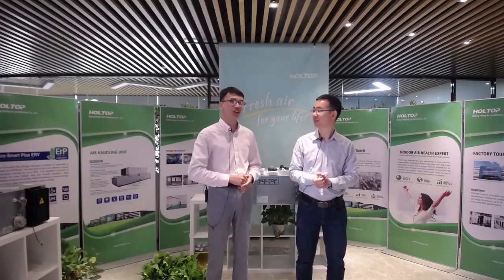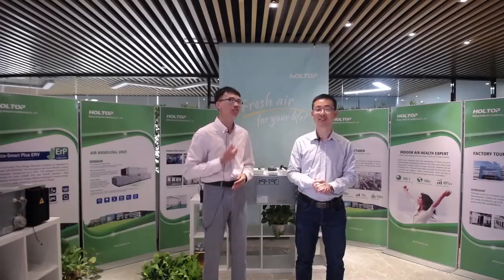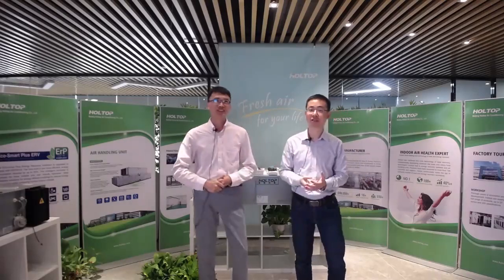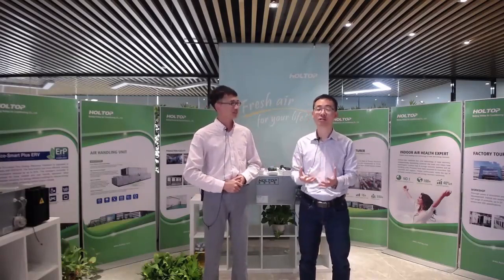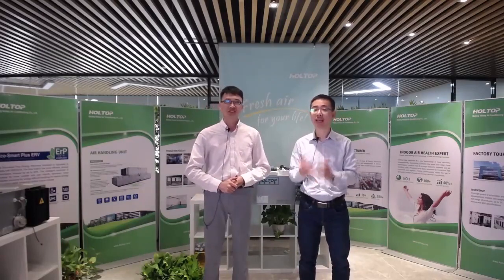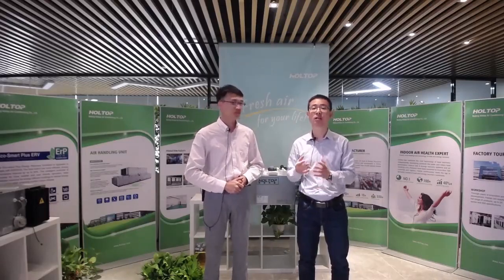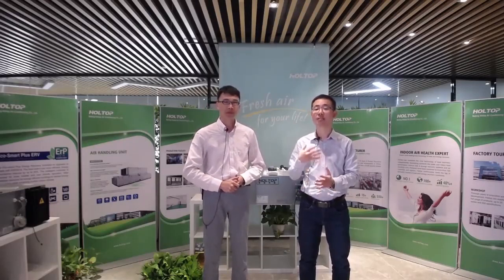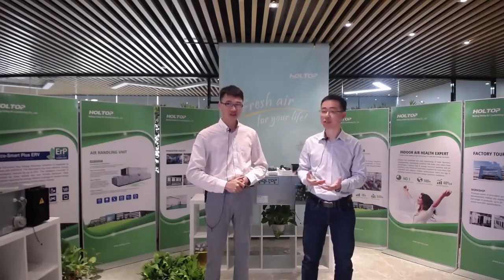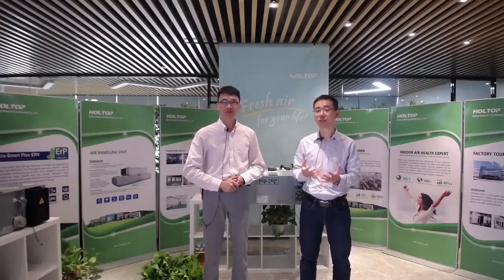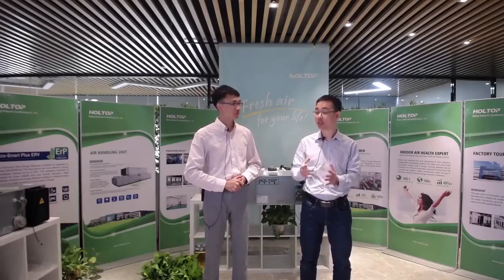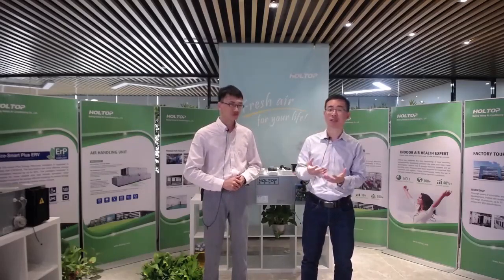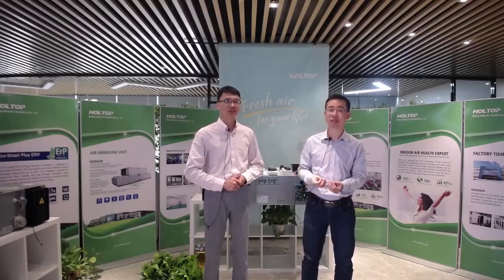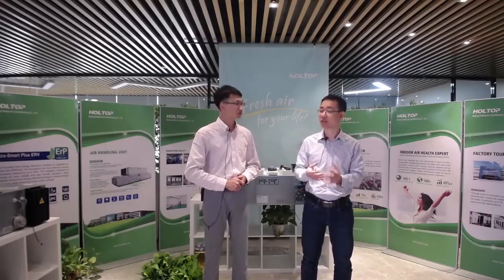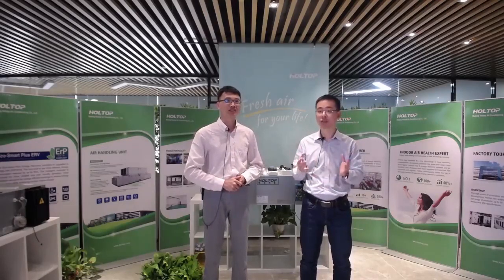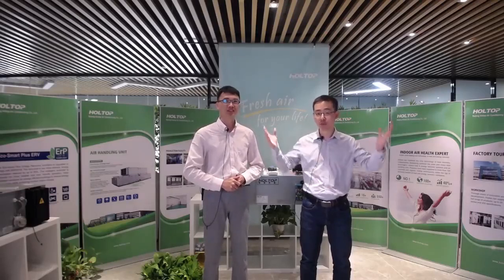So, Danny, could you please tell us what is an AHU? To begin with, a quick understanding of what an air handling unit is. An air handling unit, or air handler, or someone calls it AHU, is equipment used to condition and circulate air for the whole heating, ventilation, and air conditioning system. The AHU usually is a large metal cabinet that consists of a blower, heating and cooling coils, filters, a noise attenuator, and air dampers. The air handler connects to the ductwork and distributes the conditioned, heated or cooled air throughout the whole building.